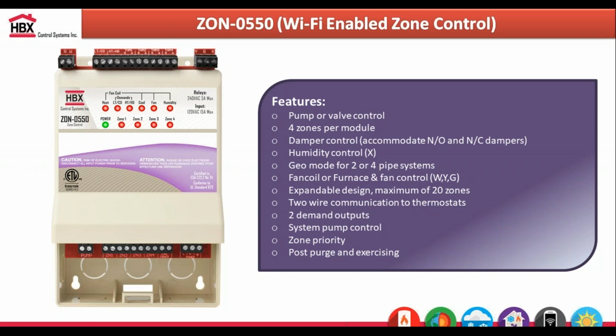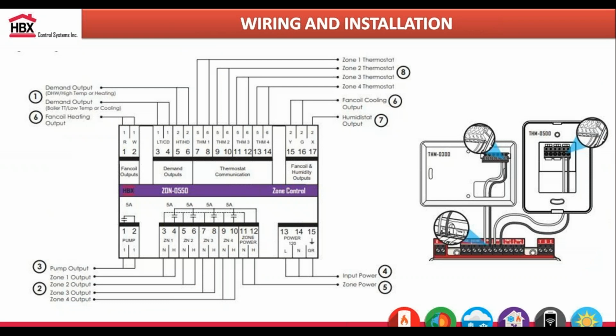So that makes it real nice in terms of how you want to implement different equipment on the zone controller. In terms of wiring, it's very straightforward. It's just 120 to power up the unit itself. You also provide power to your zone outputs at the bottom, so you would just put whatever power onto pins 11 and 12. You could put 120 in there. Again, it's rated up to 240 at 5 amps. Whatever power you put into pins 11 and 12 gets distributed out to your zone outputs for zone 1, zone 2, zone 3, and zone 4.